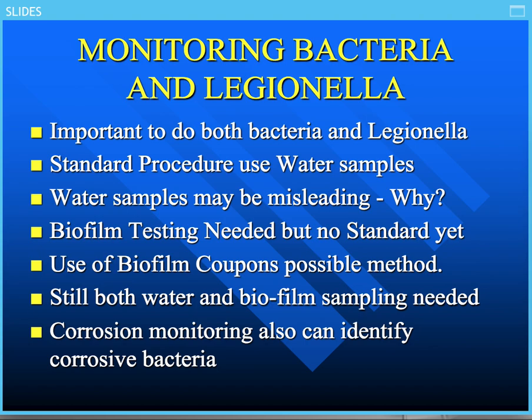Remember, biofilm is the key problem. The water is actually carrying the bacteria, and those bacteria, if they don't settle on a surface, are really not a serious problem. Let me use that as an example. If you have floating or dispersed bacteria in your system and they're not attaching to any of the surfaces and building up biofilm, that doesn't give you a problem. Okay, that's terrible, but anyway, apologize again.